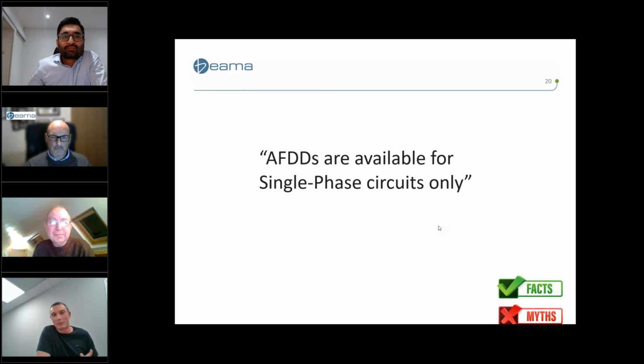Availability depends on the manufacturer, but it's important to note that BS 7671 Amendment 2, specifically regulation 532.6, only requires AFDDs to be installed on single-phase circuits. So that's where most of the availability is right now. As time progresses and things change, you may see manufacturers bring 3-phase devices onto the market.